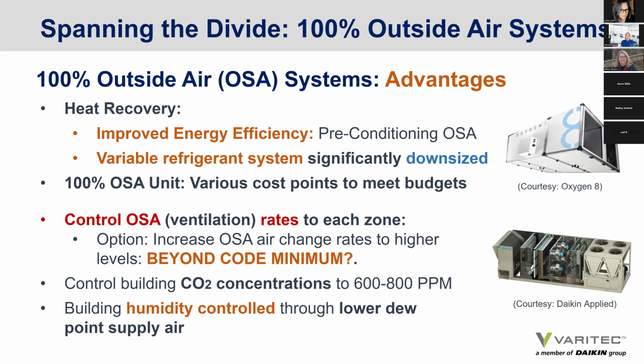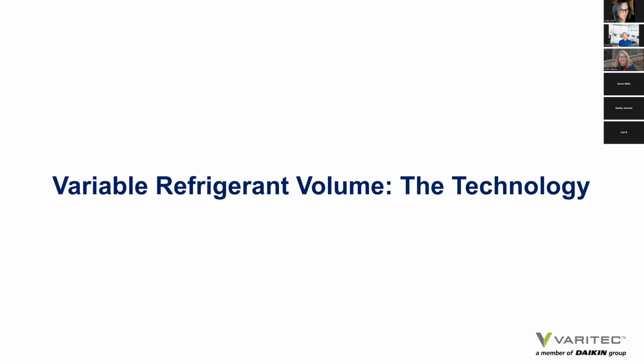So that's certainly an advantage that a 100% outside air system offers. Also, you can more effectively control your CO2 concentrations by regulating exactly your outside air flow rate to each zone. And if your outside air is properly dehumidified, which is becoming a challenge in conventional designs, then we can control outside air supply air dew point adequately to maintain appropriate humidity levels in a building.